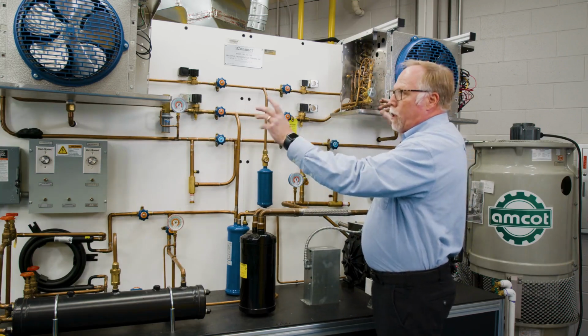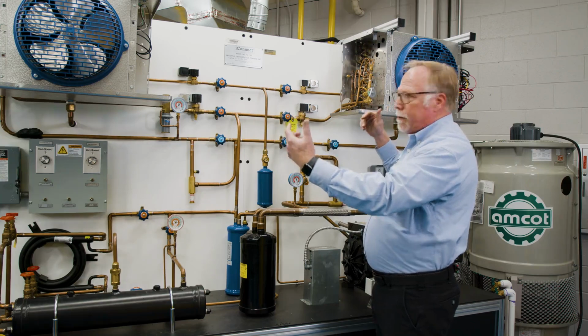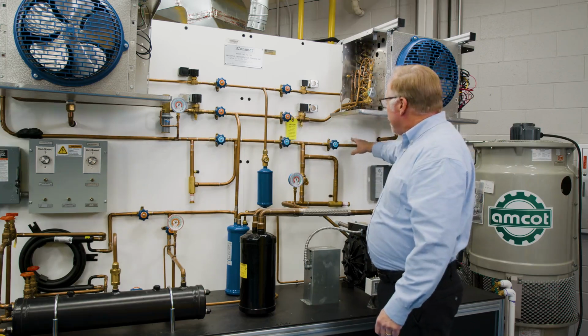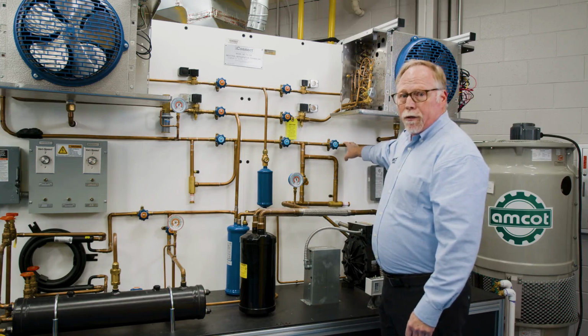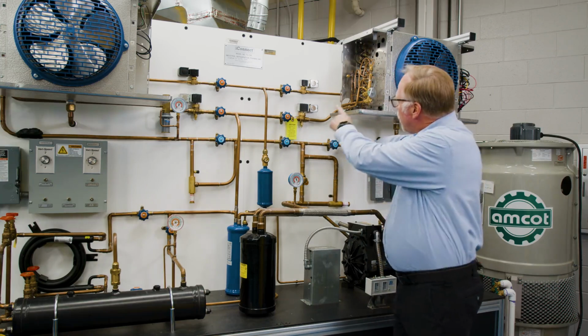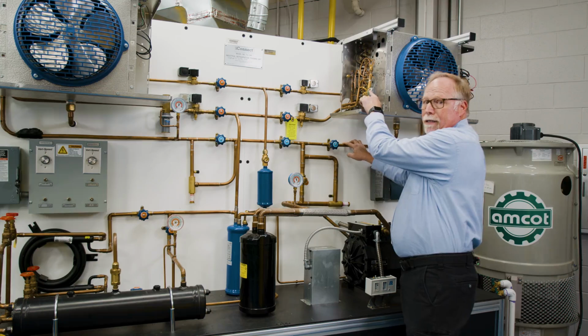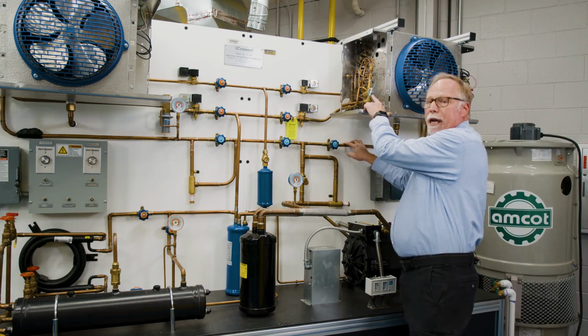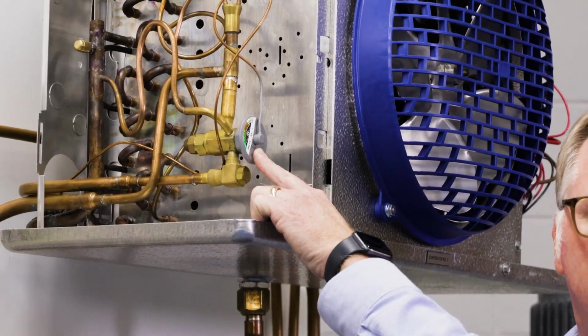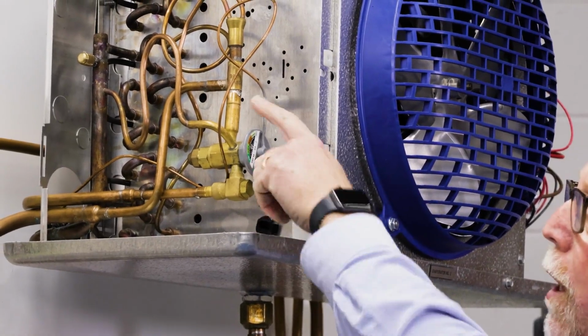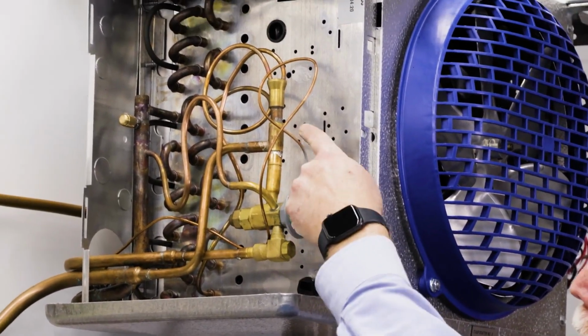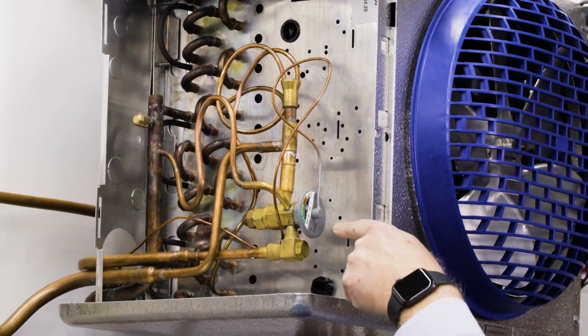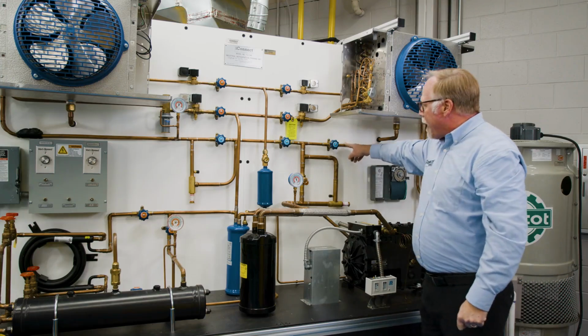Now, it's going to absorb the heat from the air. We're going to come back as a low pressure superheated gas. Here's our metering devices, and this is where we're going to change from a subcooled liquid refrigerant to the low pressure gas. It's going to enter into the evaporator. That's where it absorbs the heat. And this is where it comes back out.